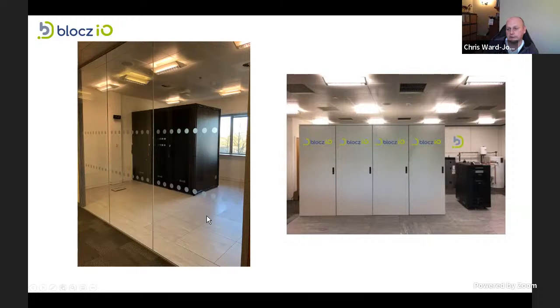On the other hand, opposite this room, we built a lab - apologies for the slightly fuzzy photo - and here you'll see some racks installed. The first thing you'll notice is there's no vents in the door, they're solid, with no airflow through these whatsoever. The reason is there's no air conditioning in the room, and we do not need to push cold air through these servers to keep them cool. We thought the best way to demonstrate that was to lock them in a metal box, because the worst thing you can do to technology is lock it in a metal box and cook it - but in this case, of course, that's exactly what we're not doing.